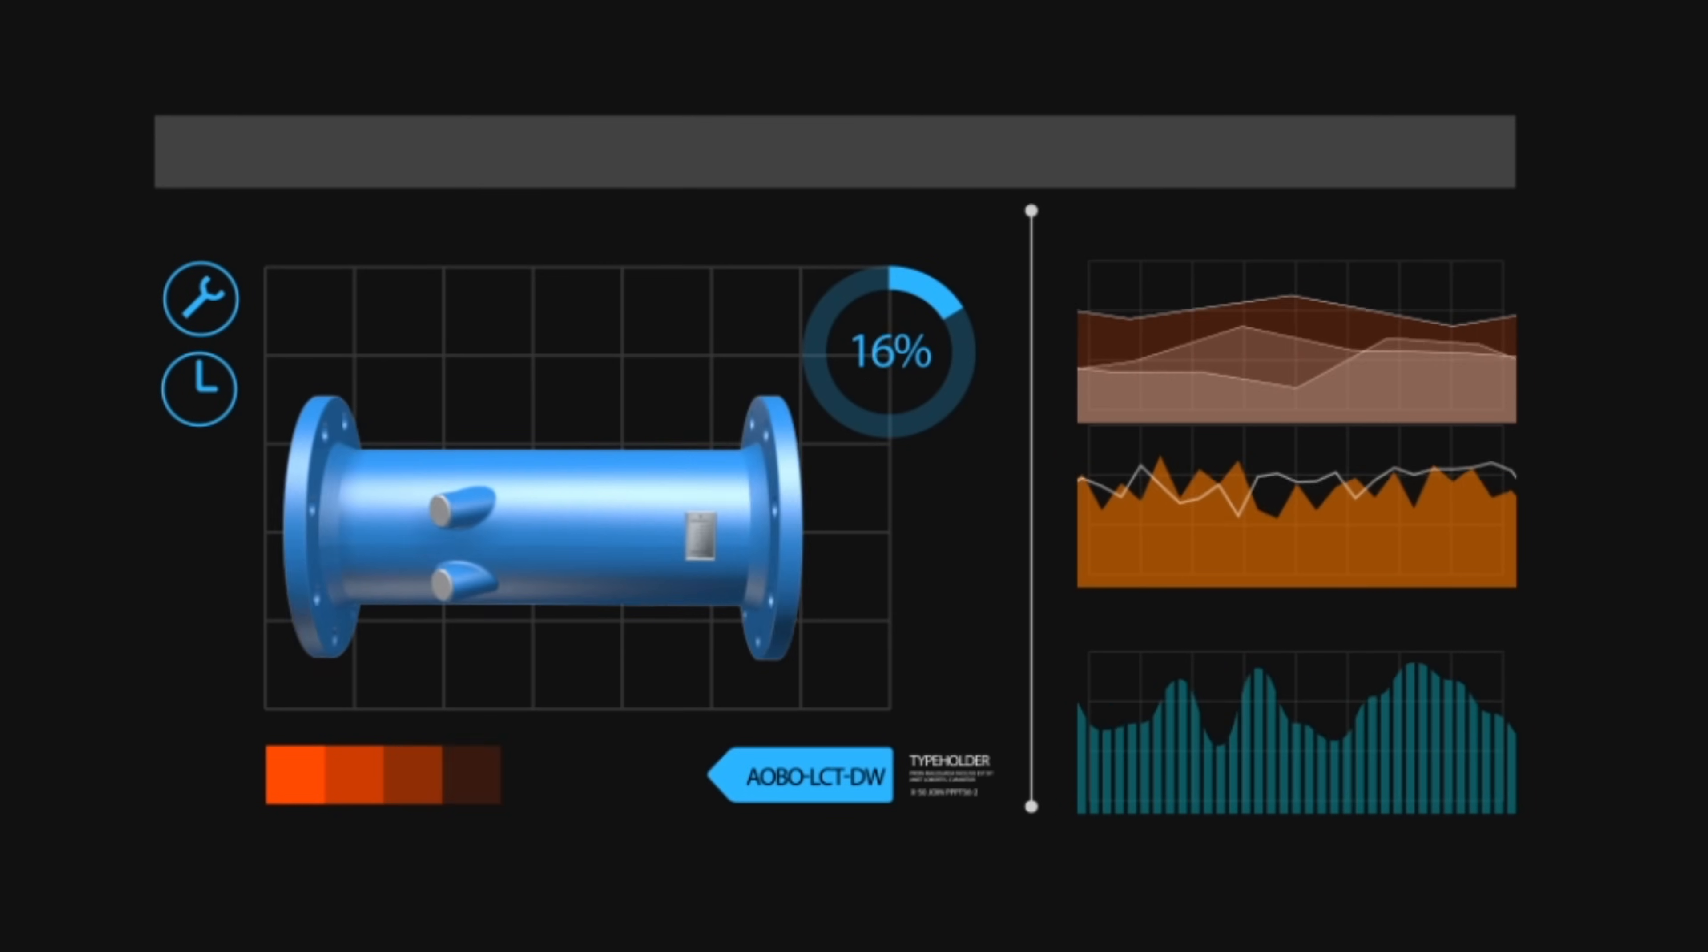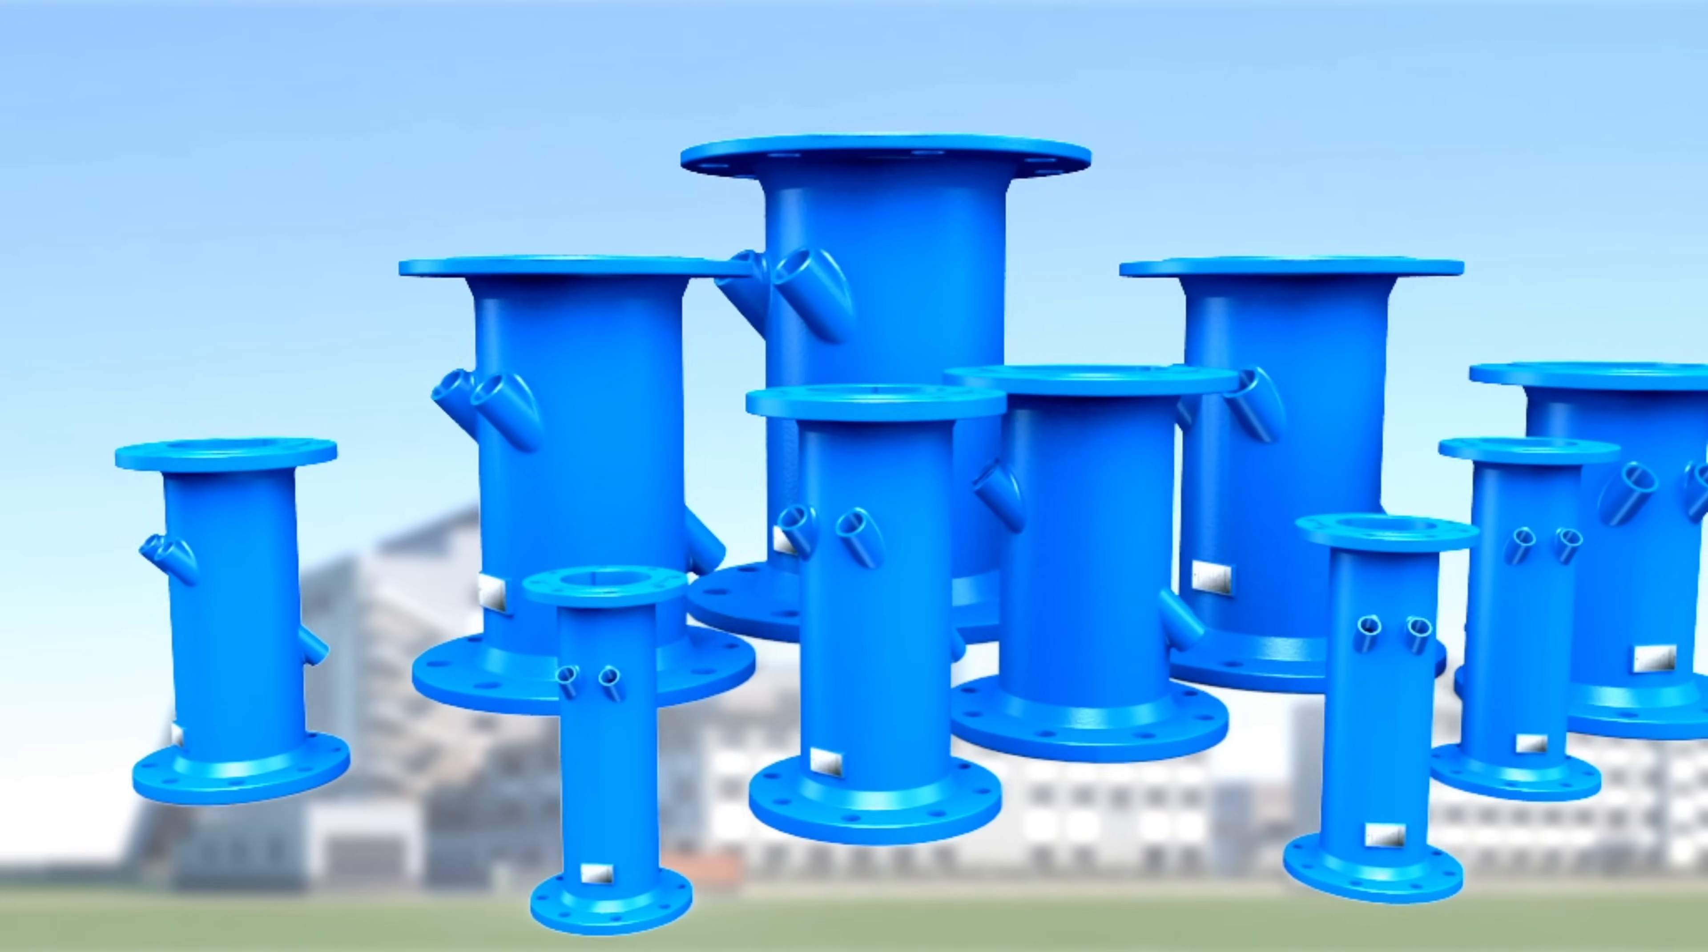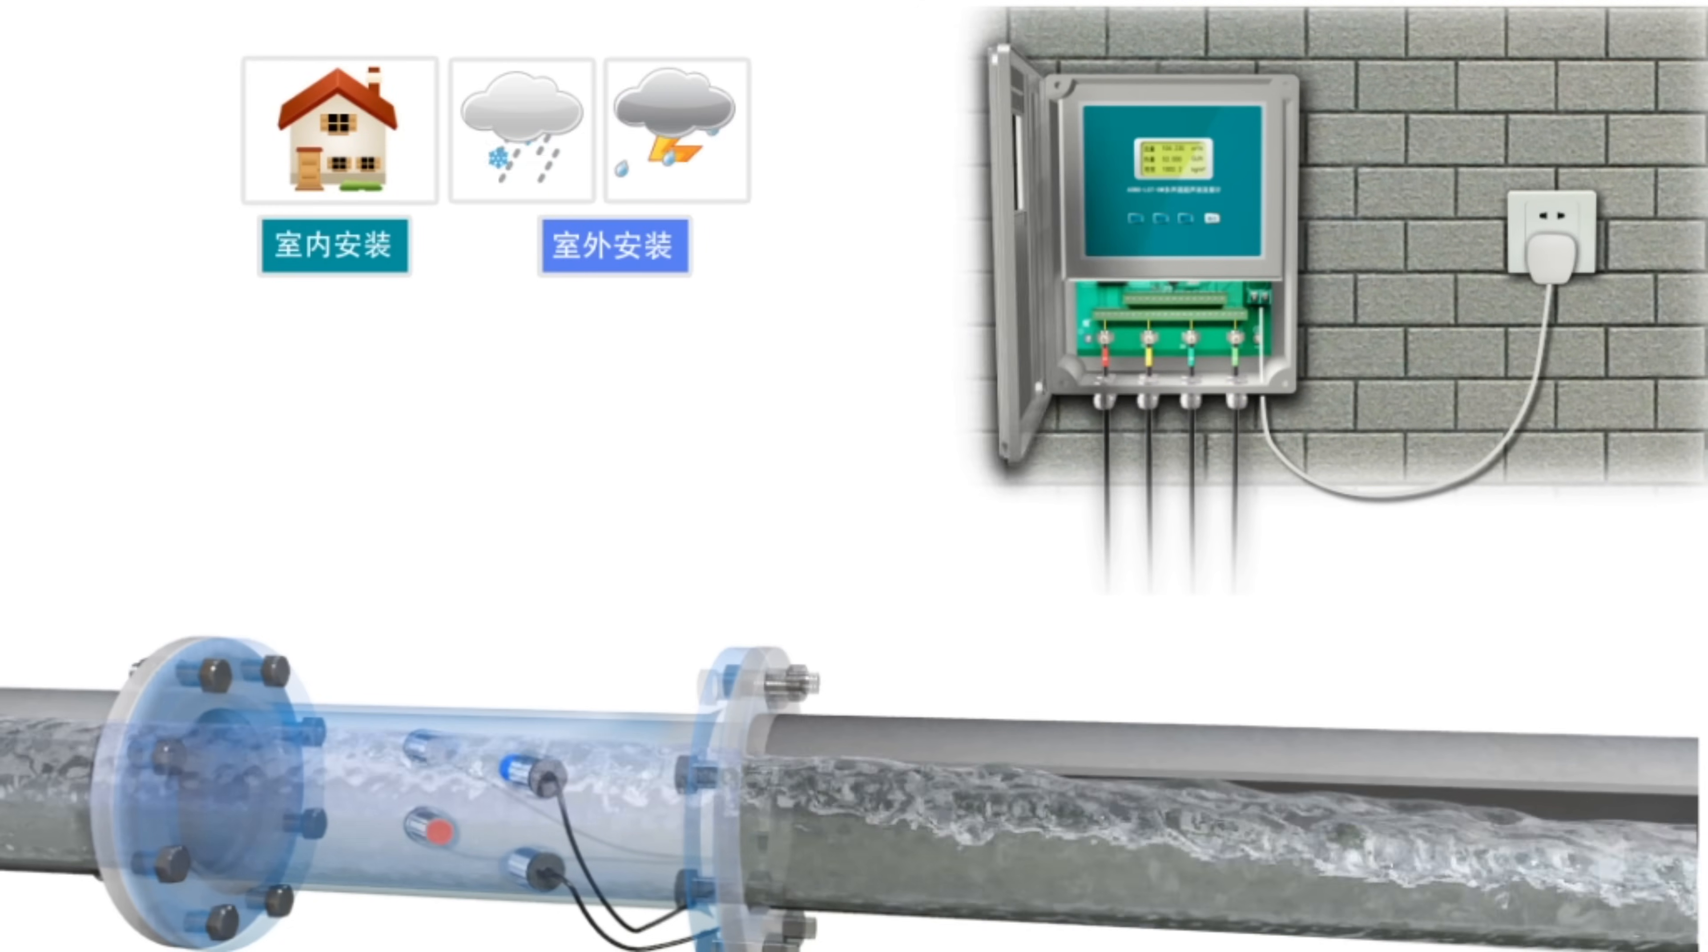The ultrasonic flow meter is able to measure medium temperature up to 150 degrees Celsius. The pipe diameter range is from DN50 to DN1600 mm. This ultrasonic flow meter is provided with IP68 protection and can be installed and used indoors or outdoors.